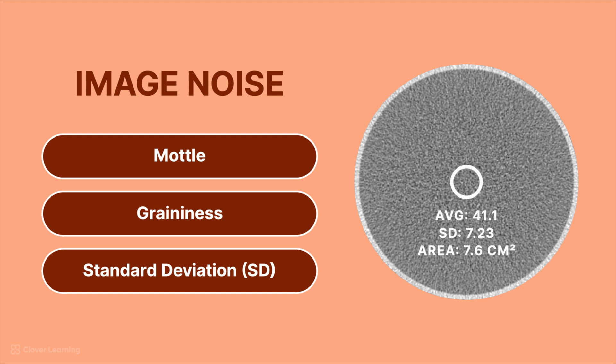If we place the ROI over this homogenous phantom, we get several numbers, including the average CT number, the standard deviation of the CT numbers, and the area of the CT numbers. If we're talking about image noise, the number that we're concerned with is the standard deviation.